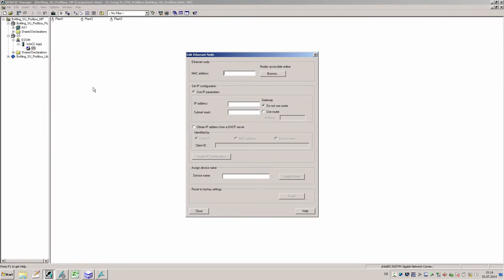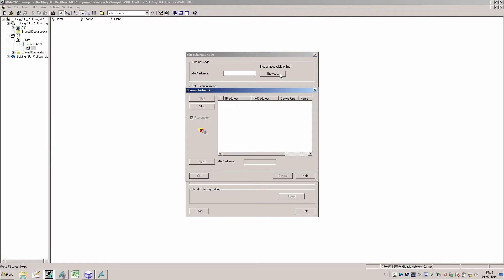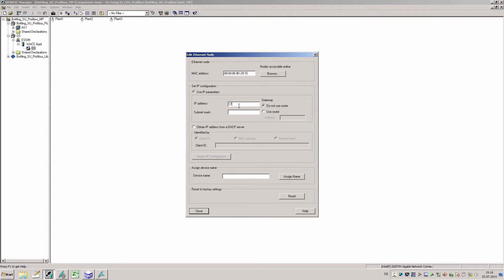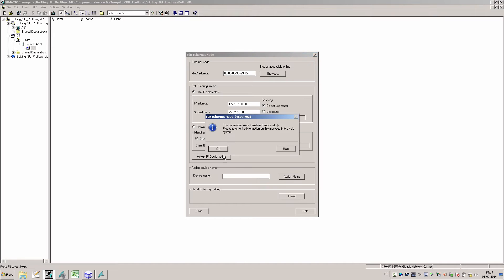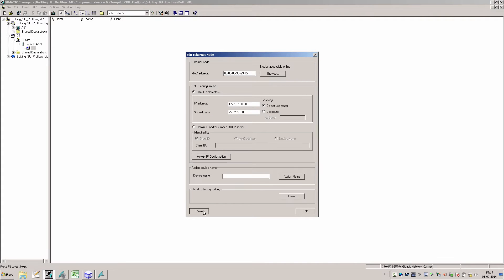In the first step I give the simulation unit a new IP address. This must be in the same sub-network as the simulation computer. In the SIMATIC manager I go to Edit Ethernet Node. Using the Browse function I search the network for all available participants. After finding the simulation unit I give it a new IP address with the accompanying net mask.